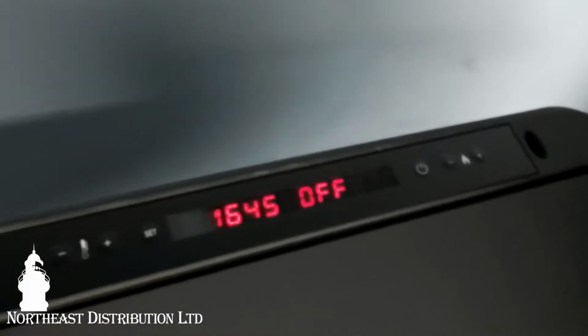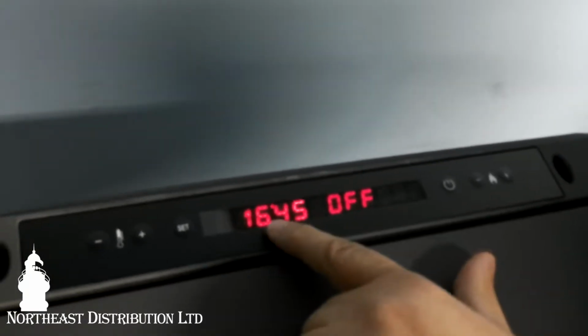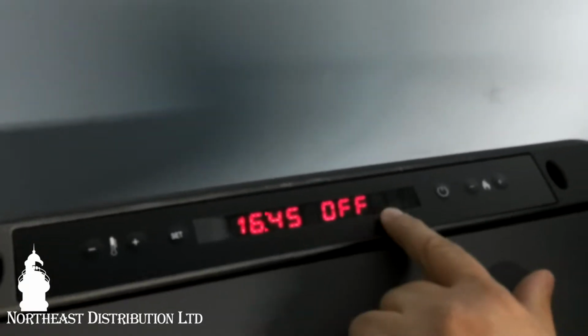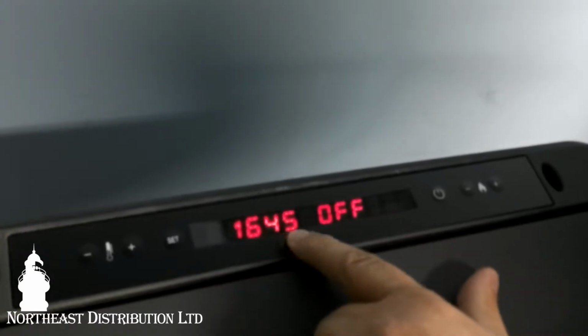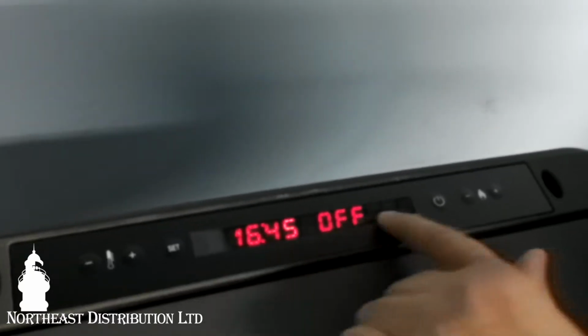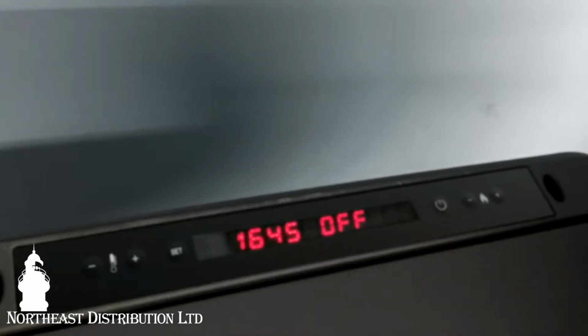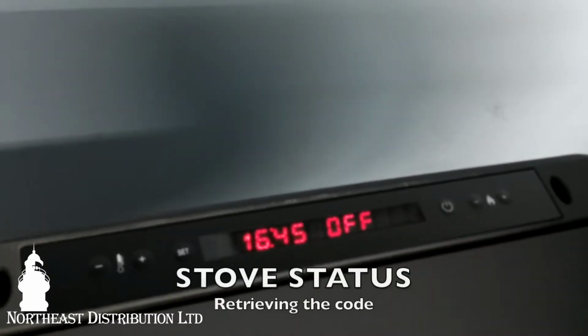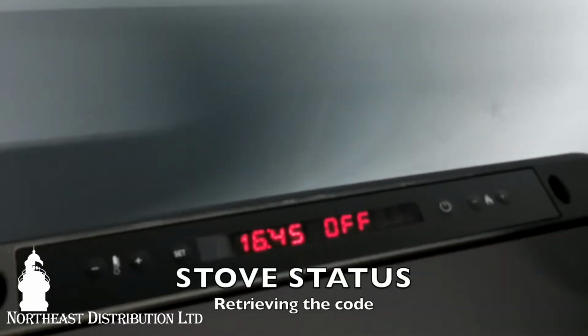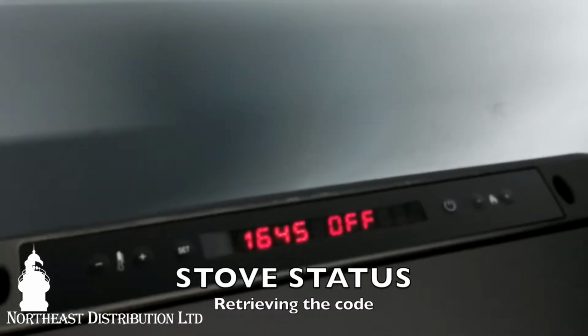If there's an error in the stove, right here you'll see the words smoke fan failure or some sort of smoke fan scroll across the screen here. When that happens, we need to go in what they call stove status to actually give us a code. And I'll show you how to do that.